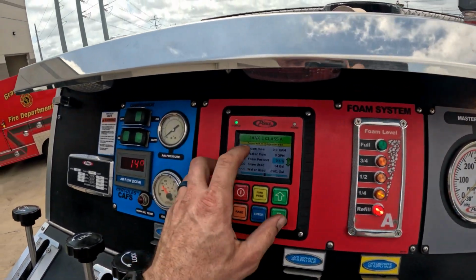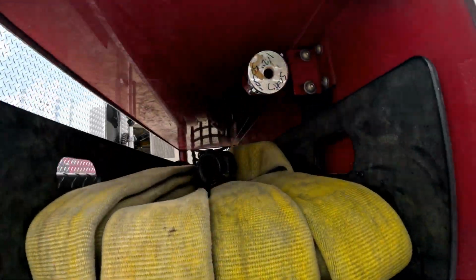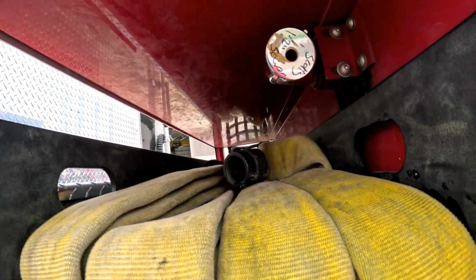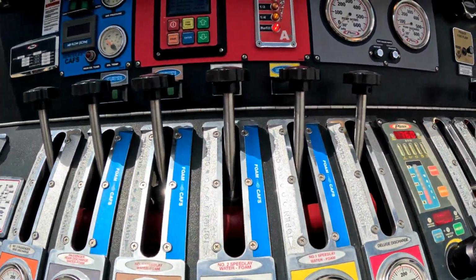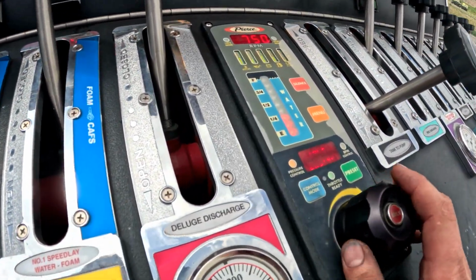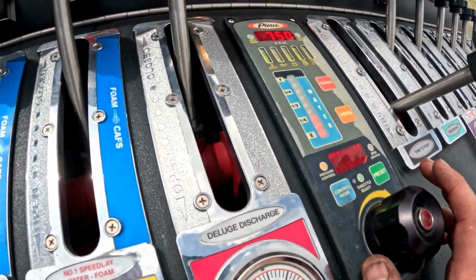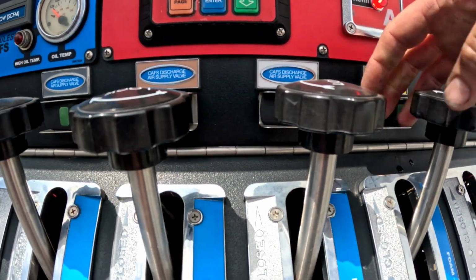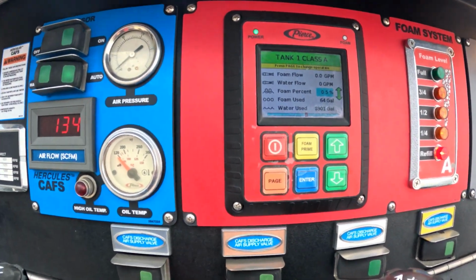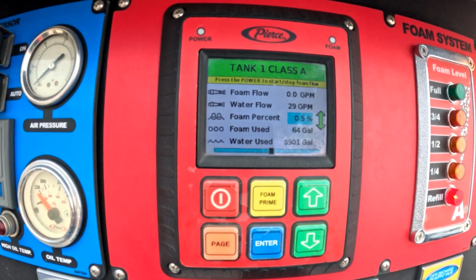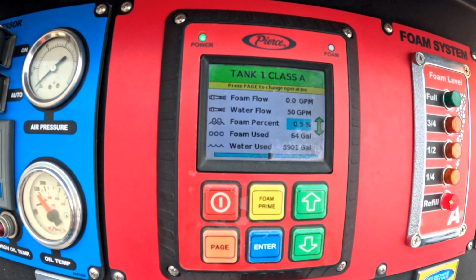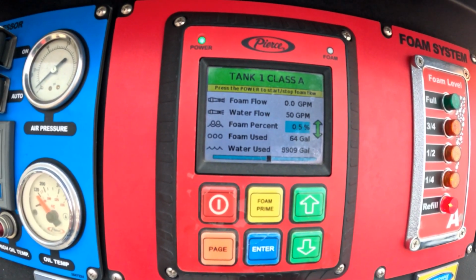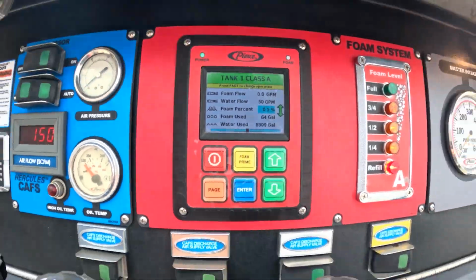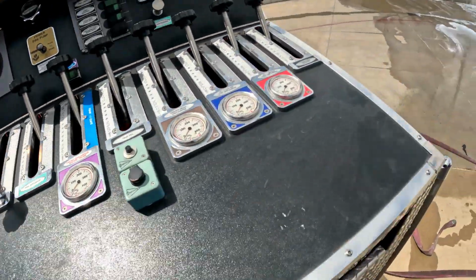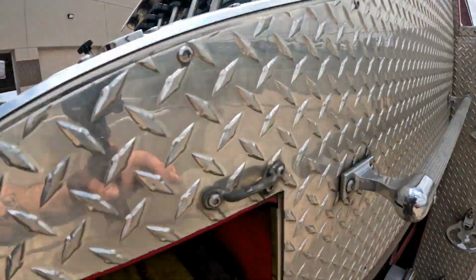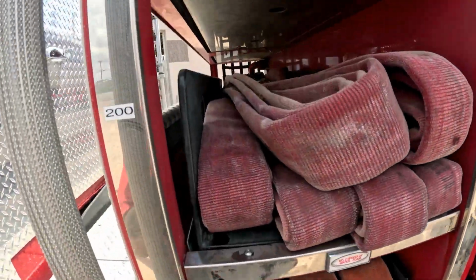So we're gonna go ahead and verify our flow calibration. So we got our 1/2 inch nozzle back on. Tank the pump open, close. Gonna open up our discharge at 45 psi. Just do 46, that's fine. It's a little bit above idle. So we're gonna open up our speedlay. And we want to see that go to 50 GPM. Right there, perfect. So that's how we verify that that is calibrated correctly. We'll close our valve. We will put our 1-inch cap on. Cap is on.